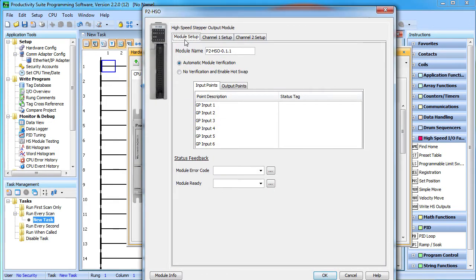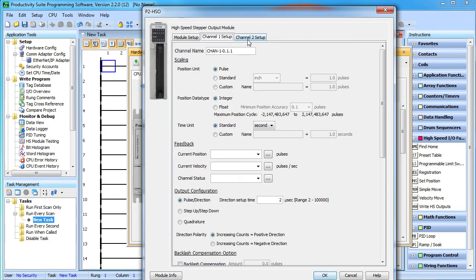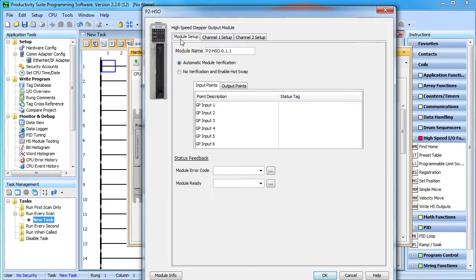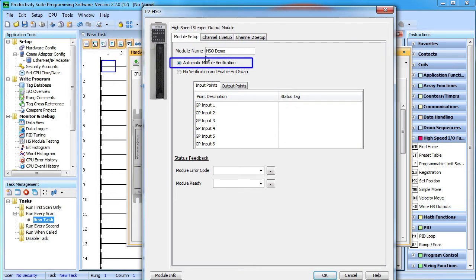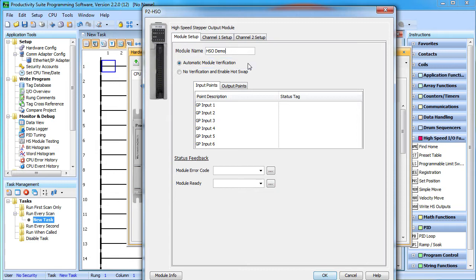We have three tabs – one for module level stuff and one for each of the two high speed output channels. Under module setup we can give the module a name. This option automatically detects and verifies the module and if someone yanks the module out while it's running it will generate an error and switch the CPU to stop mode. If you want to be able to hot swap the HSO module and not generate an error and not shut down the CPU, then select this option.